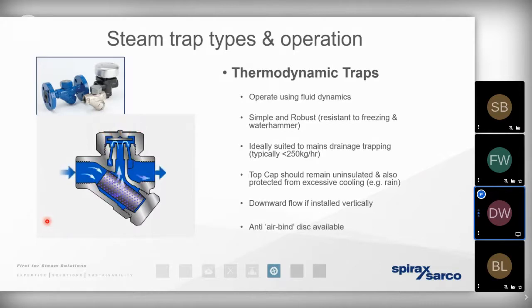by allowing the condensate that's going to exist at a very cold point once the steam system's energized. It's going to exist under pressure, but at a cold temperature. We use the steam pressure to push that condensate across the trap. It's pressurized and it moves up through a narrow orifice. The pressure of the condensate pushes a little disc into the head of the trap, and that condensate is then pressurized, at which point it can move back to the boiler house.